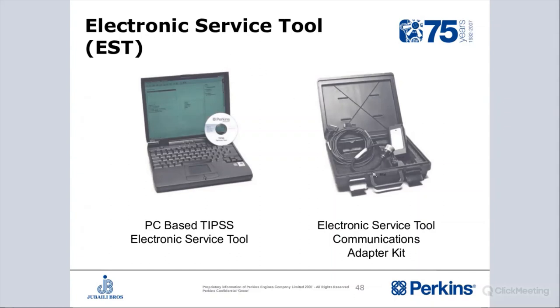The connecting tool must be the up-to-date type, called CA3, Communication Adapter 3. If you have the compact type connecting tool, we call it the compact communication adapter, you cannot use it anymore with the ADEM 5 ECMs or the ADEM 6 ECMs. You must have the CA3 type to communicate with the ADEM 5 and ADEM 6. With the compact communication adapter, you can only communicate with the ADEM 4, not the 5, not the 6. So take this into consideration.